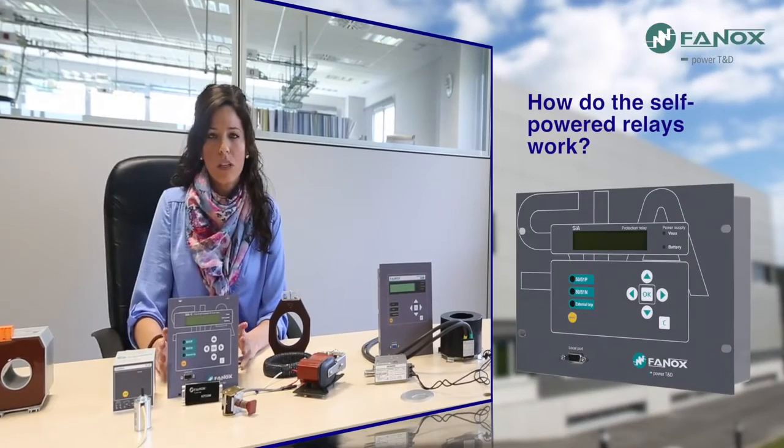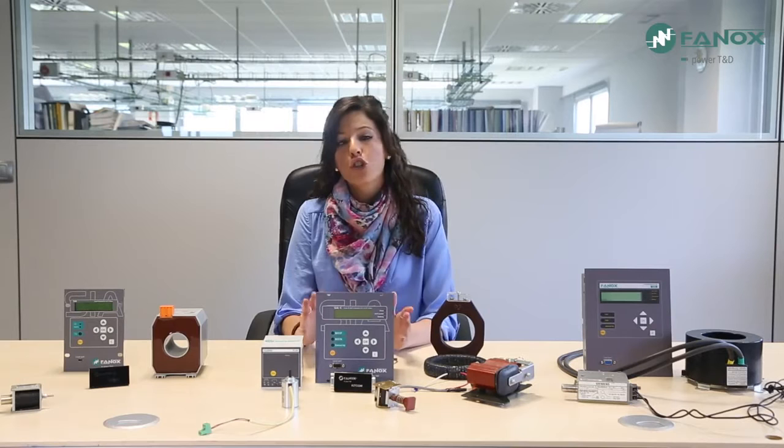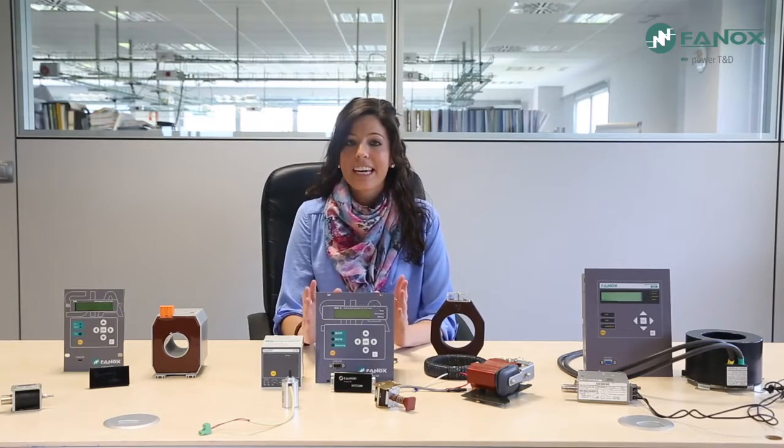How do the self-powered relays work? Self-powered relays power themselves by using the primary current of the transformation centre through the current transformers. The primary current used to feed the centre, besides being measured, is also used to obtain the energy to supply the protection relays. FANOX offers a wide range of self-powered relays.